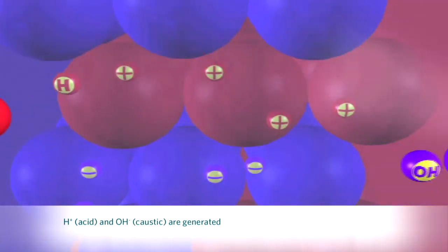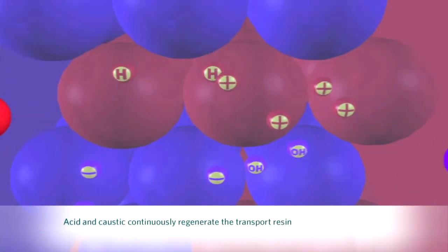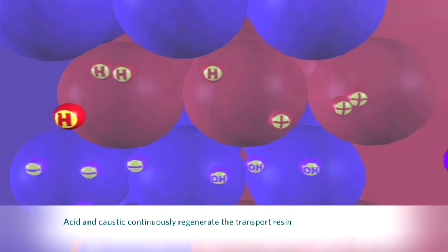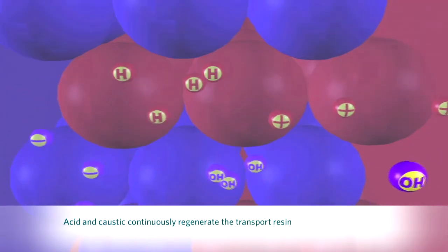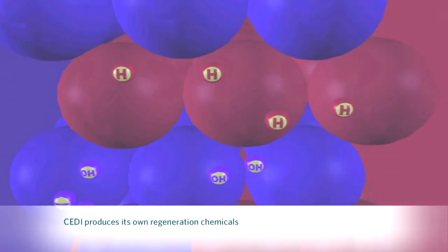The acid and caustic generated in the module regenerate the resin beads by replacing other trace ions remaining. The attachment of hydrogen and hydroxide ions to the resin beads is exactly what happens to resin beads when acid and caustic are used for regeneration in conventional deionization systems.